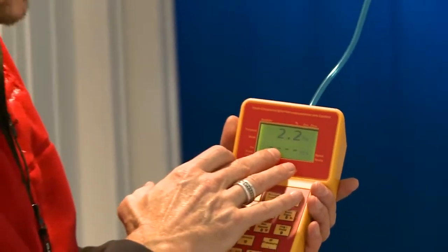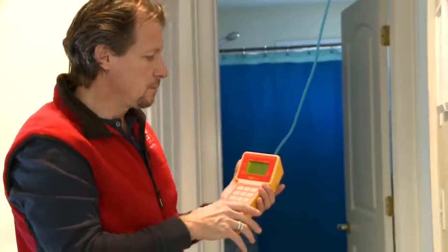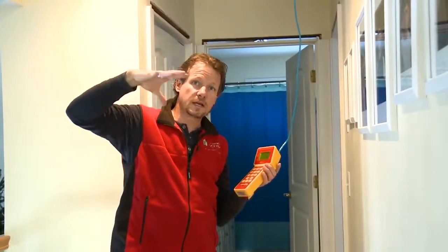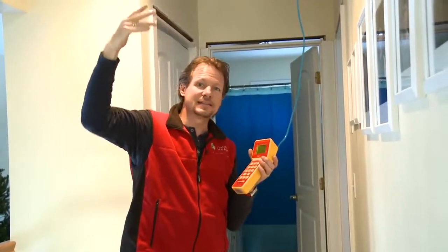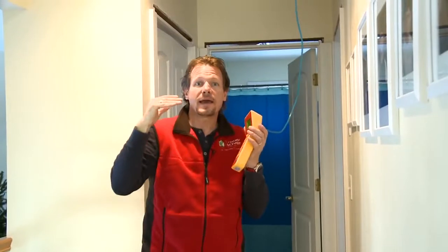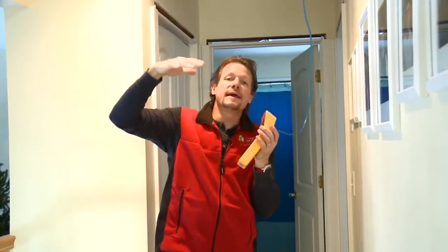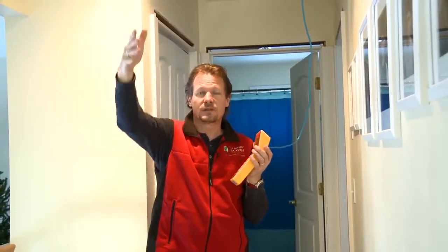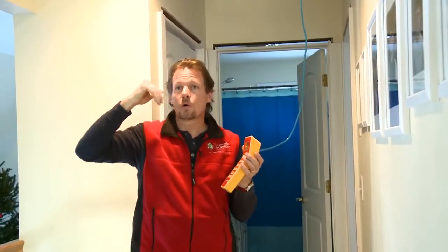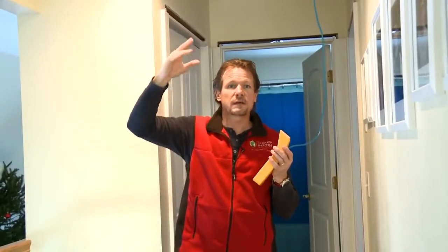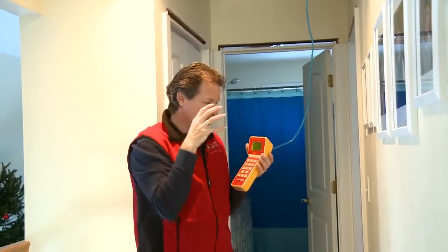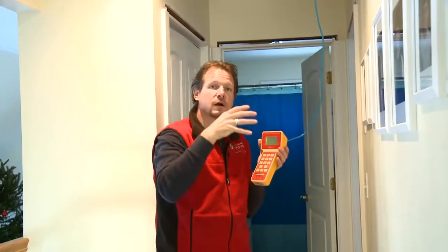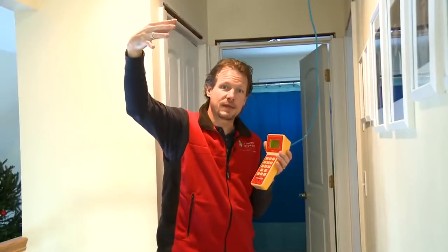And we see that we have over 2 pascals pressure difference from the second floor to the attic. So the second floor is positive and the attic is negative. And this explains why air moves through a hole in the attic ceiling or through the ducts, even when the air handler is not on, because we have ducts in the attic, we have duct leaks, or around the chimney or up through wall assemblies. Air wants to move from the inside of the house to the attic because of the stack effect, we are positively pressurized in the top of the house.